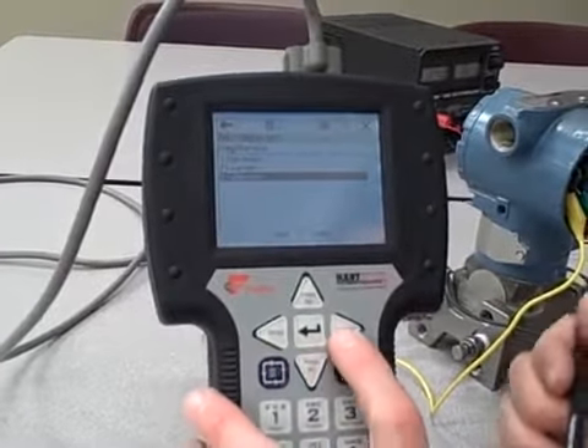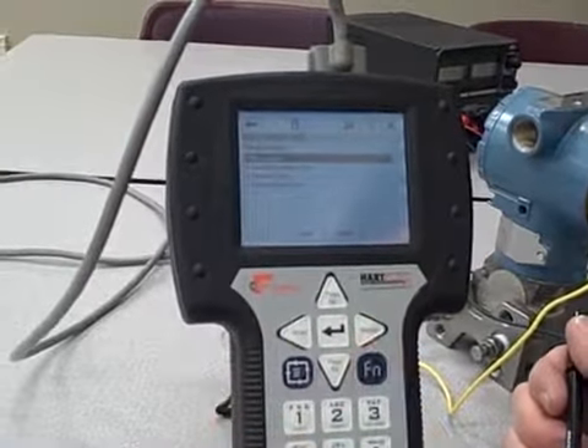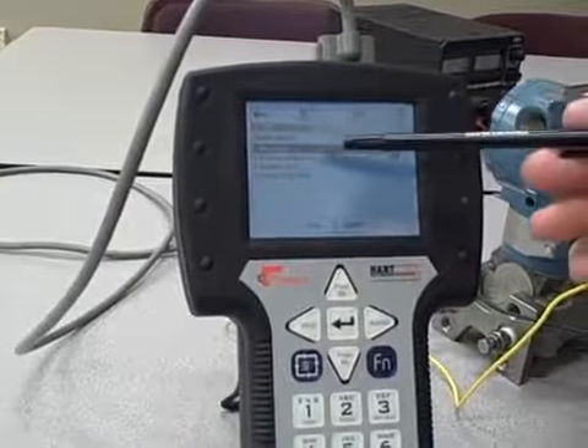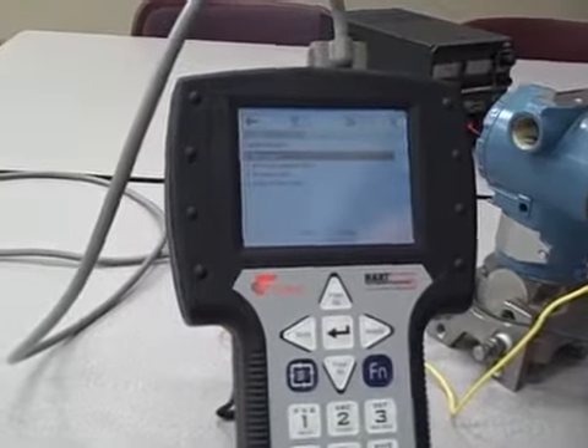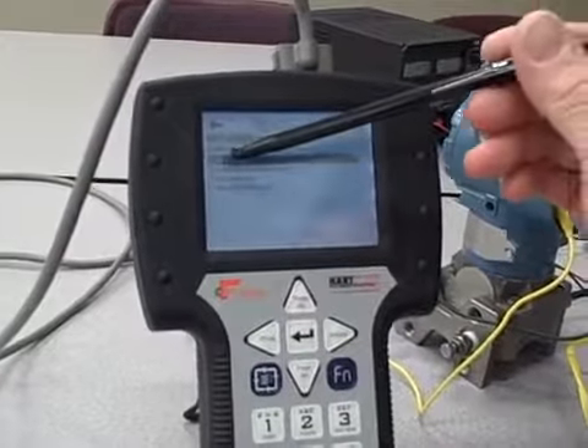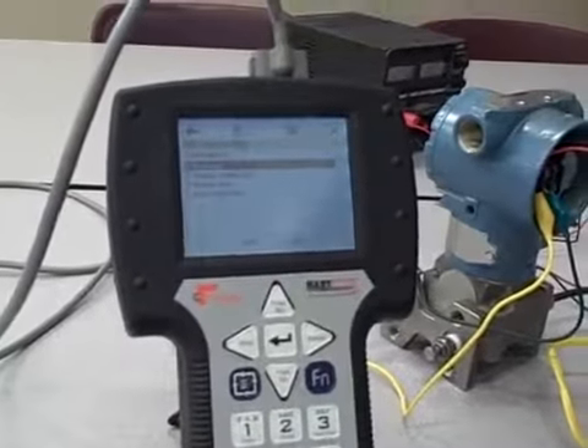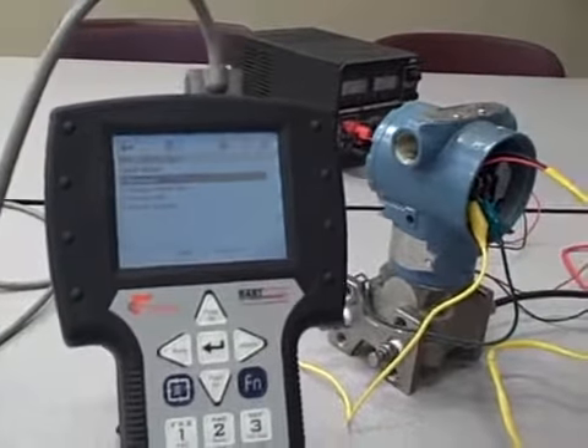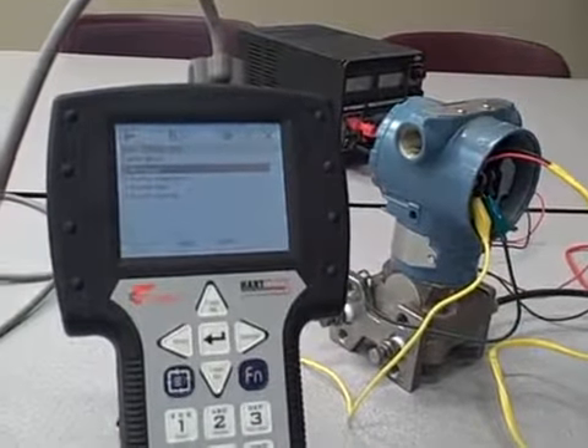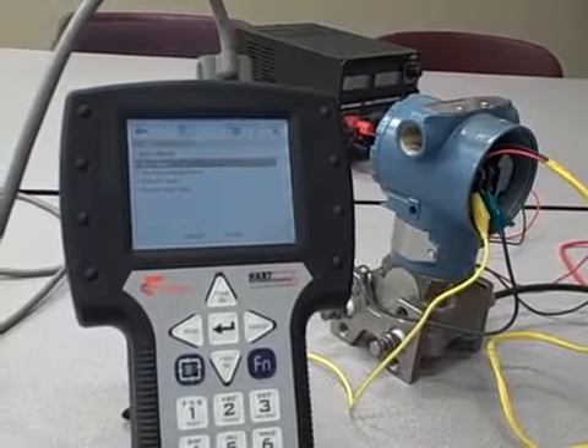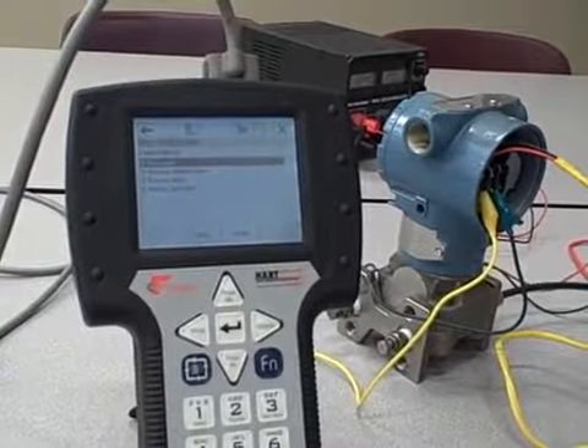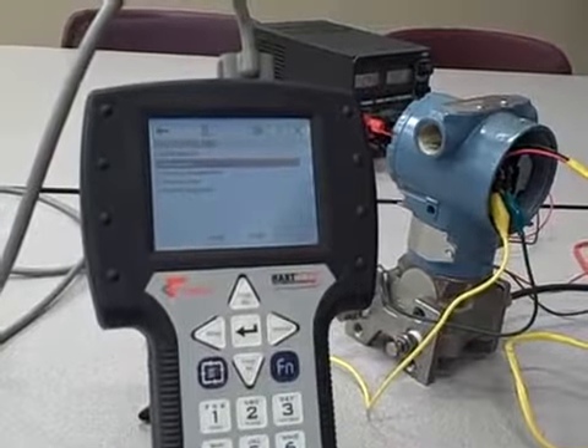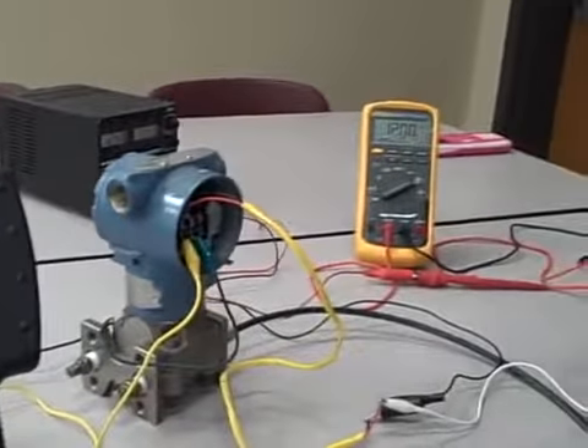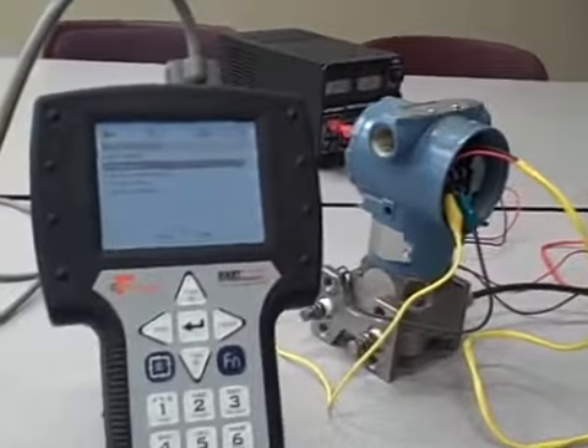Under calibration, this is a very important menu for instrument technicians. We can set the range points, which we could set from other screens too. We can do what's called an analog output trim, which tells or confirms to the transmitter what 4 and 20 milliamps looks like. For example, our last test where we forced the output to go to 20 milliamps and our Fluke meter actually read 20.01 may indicate the need to do an analog output trim.